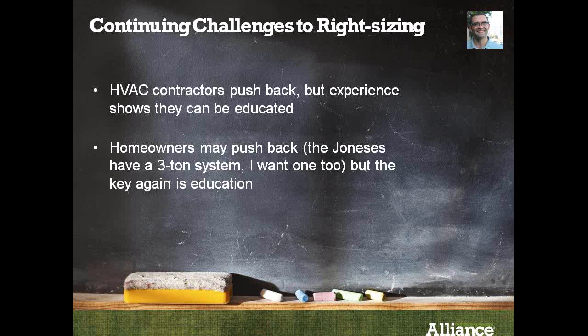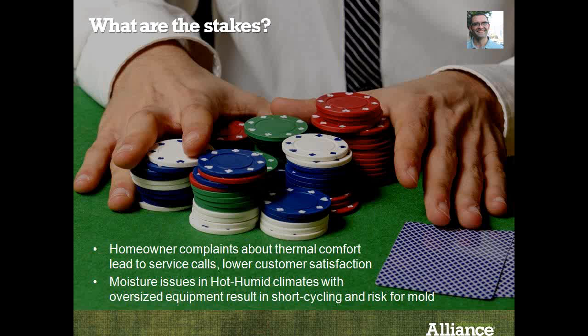the right way. The other pushback, and the other problem that we can run into, is homeowners will complain that they don't have an air conditioning system that's as big as the neighbors have. So the Joneses have a 5-ton, why do I have a 3-ton? Am I not getting the right value for my money? And what does this mean for comfort? The stakes can be pretty high related to comfort. If you have a lot of complaints, then you're going to get a lot of callbacks.